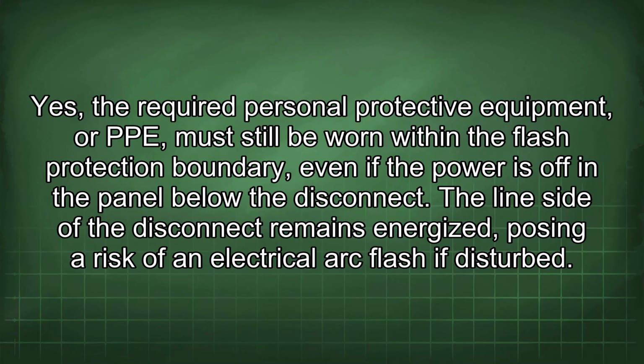Yes, the required personal protective equipment, or PPE, must still be worn within the flash protection boundary, even if the power is off in the panel below the disconnect. The line side of the disconnect remains energized, posing a risk of an electrical arc flash if disturbed.